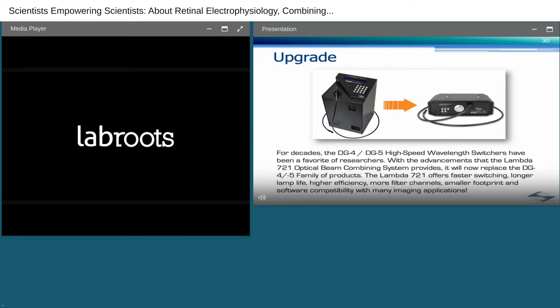The final mode that I would like to talk about is Setup. In this mode, the power on state, either on or off, and the output power level of an LED can be configured. Turn the selection knob until the Setup mode prompt appears. Press the Yes button. The display will show the power settings for the first LED. To change the settings, use the selection knob to adjust power from 100% to 0%. Use the On button to turn the LED on, the Off button to turn it off. The Next button advances to the next LED without saving any power level adjustment or LED state. The Enter button saves settings and advances to the next LED. Pressing Enter on LED 7 exits setup mode and goes to the Use Ring Buffer prompt. Just a few additional comments that you may have already seen in our newsletter. For decades, the DG4, DG5 high-speed wavelength switchers have been a favorite of researchers.